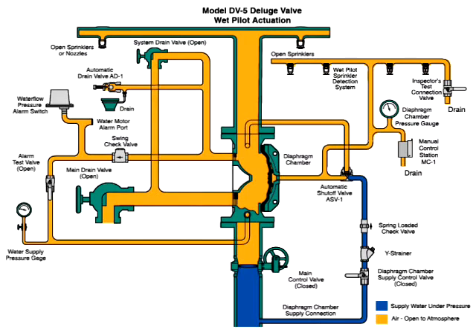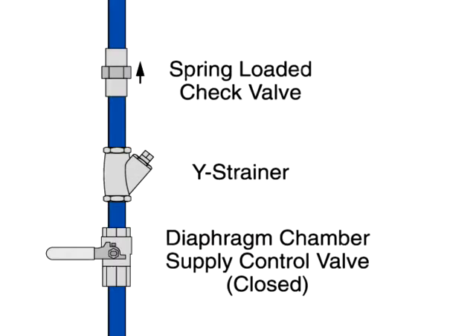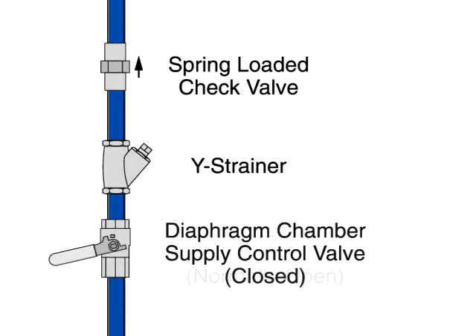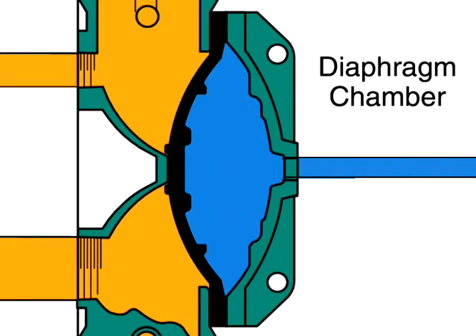Once the system stops discharging water, close all drains except the main drain valve. Depress the plunger of the automatic drain valve to verify that it is open and the system is drained. Clean the Y-strainer in the diaphragm chamber supply connection trim. Reset the wet pilot actuation system by replacing operated pilot sprinklers.